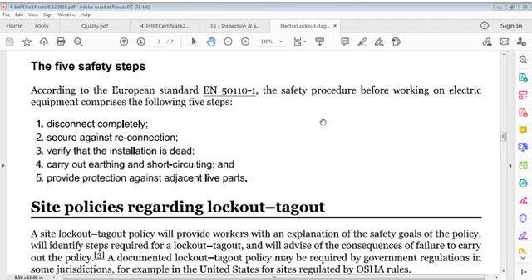I repeat, this is the European standard, and it says the safety procedure before working on electric equipment comprises the following five steps. Number one, disconnect completely. Secure against reconnection. Verify that the installation is dead. Carry out earthing and short circuiting and provide protection against adjacent live parts.